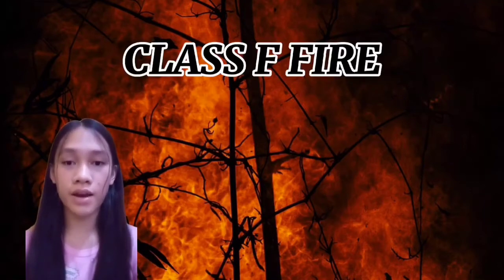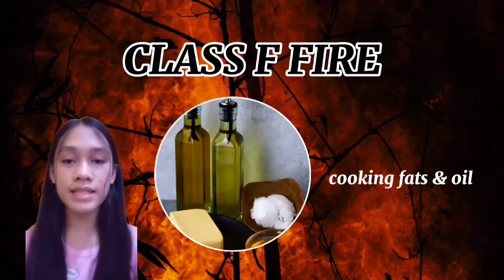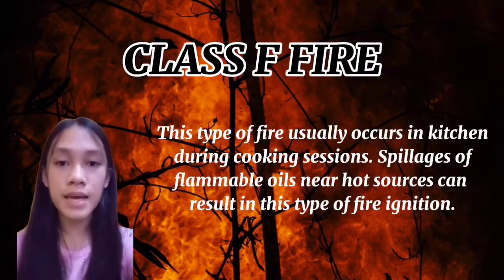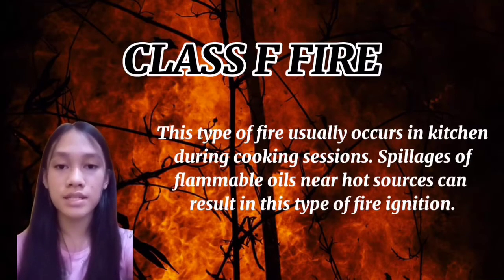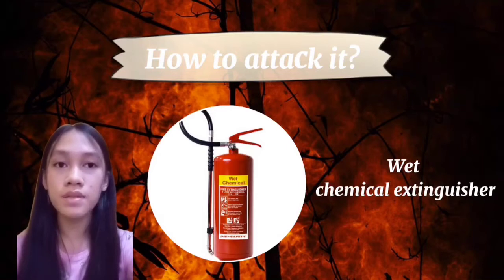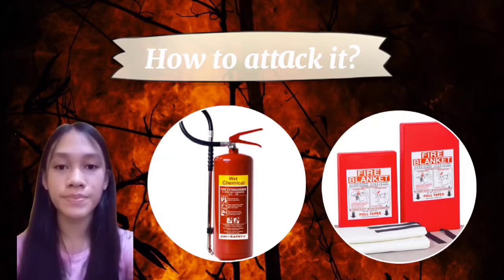And last but not the least, the Class F fire, which involves cooking fats and oils. This type of fire usually occurs in the kitchen during cooking sessions. Spillages of flammable oils near hot sources can result in this type of fire ignition. A wet chemical extinguisher is the only type of extinguisher approved for this usage. For small Class F fires, we can also use a fire blanket.